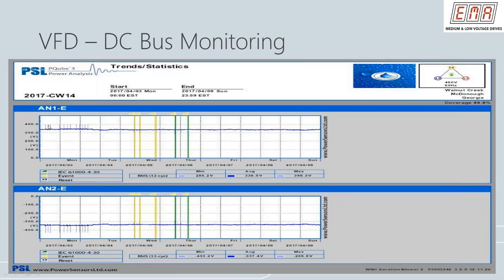So as a result, we have 400 volts here on the positive DC, and over 450 volts roughly on the negative side. So combined, peak-to-peak voltage of roughly 850 volts. Our DC bus capacitors are rated for 800 volts maximum on a 460 volt power line. The reason that's the case is our nominal DC should be square root of 2 times the input voltage.